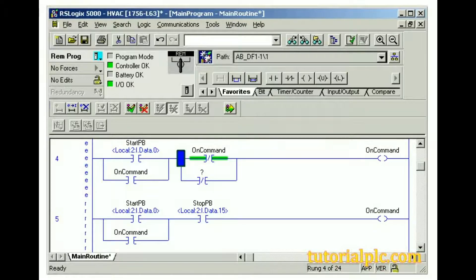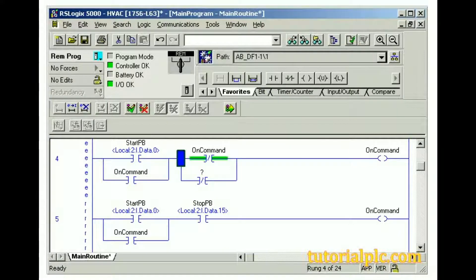Because accepting a change online can cause dangerous situations, there are more steps to verify a rung when online. The number of steps depends on the current mode. In the remote program mode, we must perform the following actions: First, we must verify the rung, which is optional, and make any corrections. Then we must accept the edits.